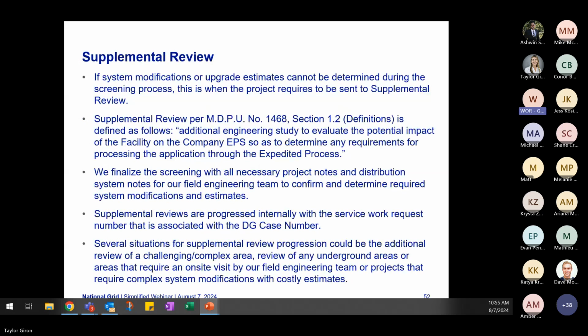Supplemental review: if system modifications or upgrade estimates cannot be determined during the screening process, the project is sent to supplemental review. Supplemental review, per MDPU number 1468, section 1.2, is defined as additional engineering study to evaluate the potential impact of the facility on the company EPS, so as to determine any requirements for processing the application through the expedited process. We finalize the screening with all necessary project and distribution system notes for our field engineering team to confirm and determine required system modifications and estimates. Supplemental reviews are progressed internally with the service work request number associated with the DG case number.